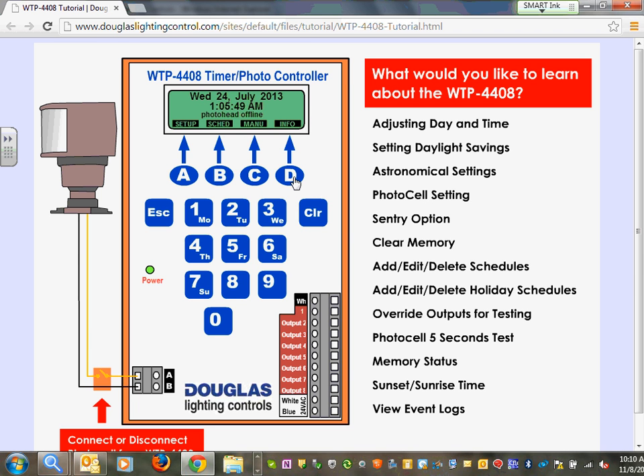You can do the programming in your laptop, download it into the panel. Not with this system. Okay, so in the next system up, so we've gone from this system to this system, which is web-based. If I get an IP address, if I get access to their IP, and typically, and it happens all the time, right? A school will want us to do something, or prior to doing the startup, actually going out and training the owner, they'll grant us access for 24 hours.